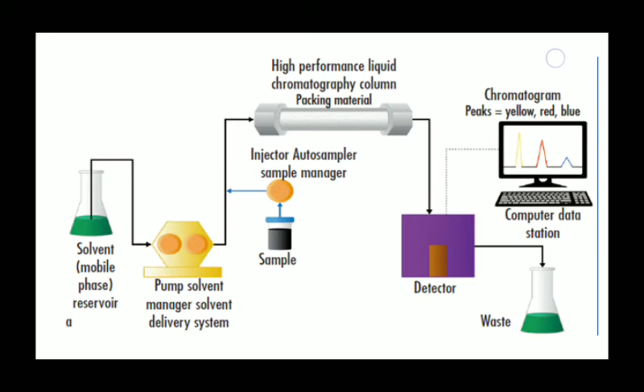The internal diameter of the HPLC column is an important parameter that influences the detection sensitivity and separation selectivity in gradient elution. It also determines the quantity of the analyte that can be loaded onto the column. Larger columns are usually seen in industrial applications such as the purification of drug products. Low ID columns have improved sensitivity and lower solvent consumption at the expense of loading capacity. Larger ID columns over 10 mm are used to purify usable amounts of material because of their large loading capacity.